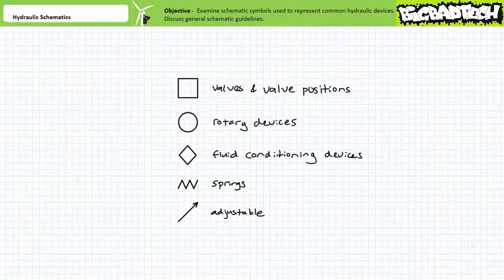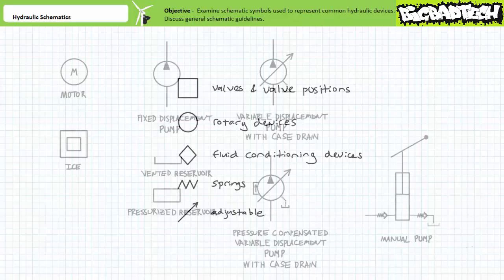First, valves and valve positions, as we learned in the directional control valves lecture, are represented schematically as boxes. Rotary devices like pumps or hydraulic motors are represented schematically, appropriately enough, as a round circle. Fluid conditioning devices like filters or heat exchangers are represented schematically as diamonds. Springs look like springs. If the spring or valve is adjustable, a slanting arrow indicates this feature. That's really about it for general schematic guidelines. Try not to hurt yourself.